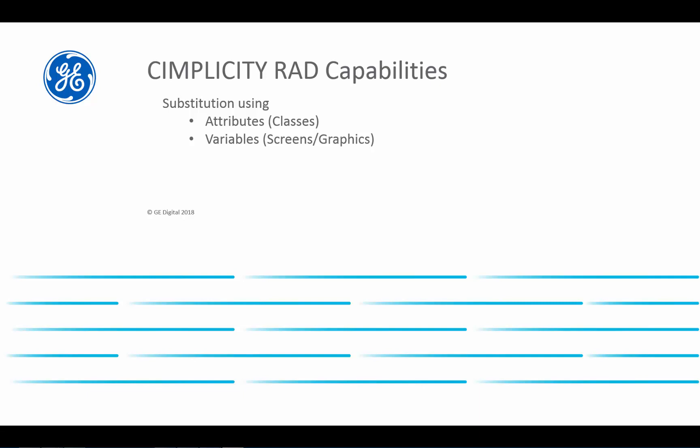This concept is called substitution, and it allows you to define attributes for classes and objects in CIMPLICITY, or variables at the screen and graphic level. You can use these within your expressions and class definitions to substitute in values dynamically at runtime or object creation time, allowing you to define things once and reuse them multiple times.